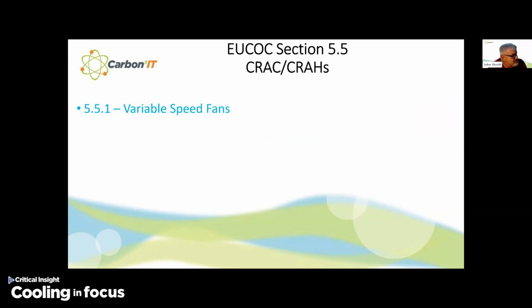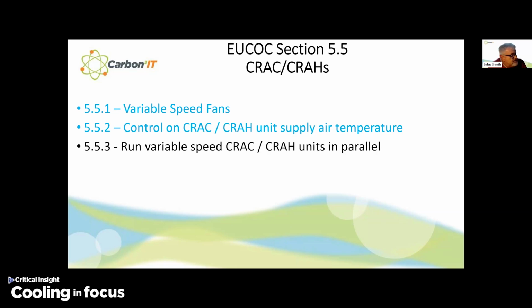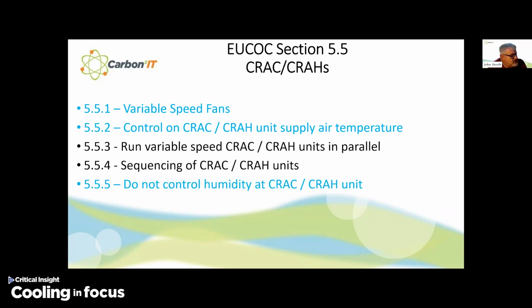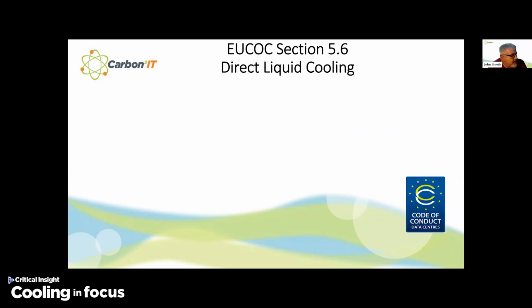For CRACs and CRAHs, variable speed fans, control on supply air temperature, not return. Run variable speed CRACs in parallel. Sequencing of CRAC/CRAH units. Do not control humidity at CRAC unit. Cooling size and selection. And then for direct liquid cooling, and this is quite disappointing personally, there's only one best practice.